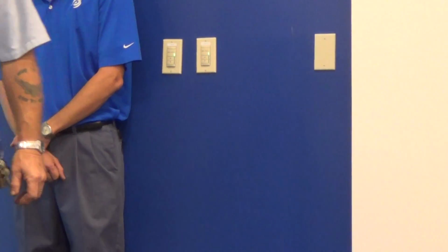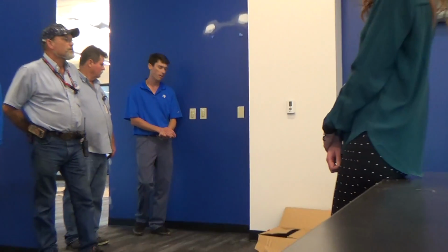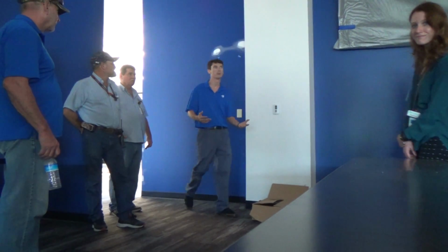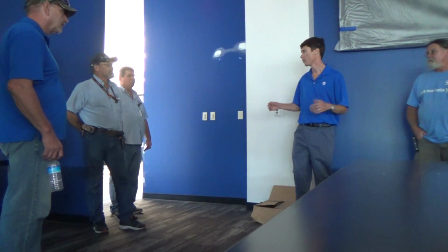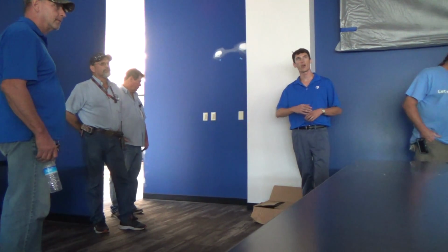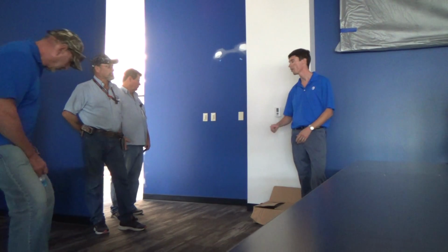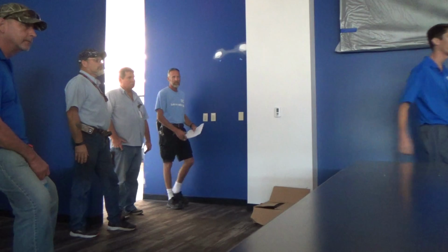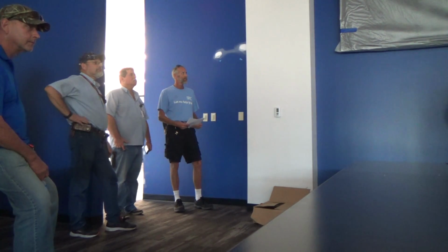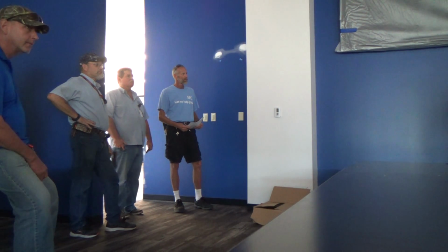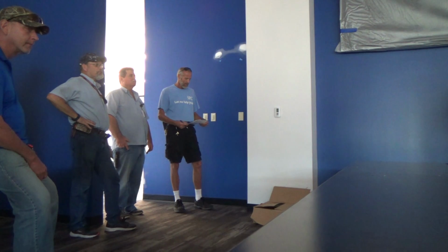And when you leave, the lights will turn off automatically. Now, like what Scott was saying downstairs, if we hit this button off, and now we walk out the room, it's going to stay like this. You're going to have to come back in and hit it on. So anywhere where there's automatic lights, if they hit the button off, they're going to stay off until you hit the button again. That's because if now we walk out the room, the sensor is going to turn the lights back on, right? So we tell it to turn off, and the lights stay off. And that's whether it's a manual on area or an auto on area. You hit the button off, it'll stay off until you hit the button on again.